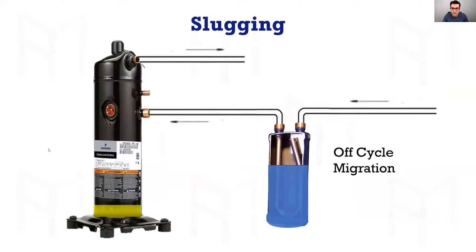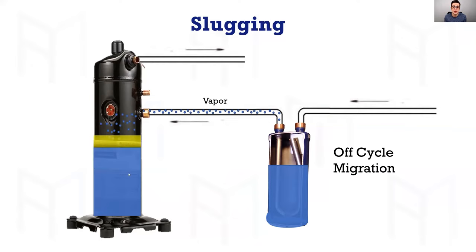Let's get into it. Here's an example of a system with the compressor off. How a slug happens in a refrigerant-cooled compressor — scroll compressors, large semi-hermetic compressors like 3D, 4D, 6D Copeland compressors. When they're off, refrigerant can travel through the system as a vapor — from the evaporator, or even from the accumulator. If that accumulator is warmer than the actual compressor, refrigerant will start traveling through and condense down into the oil.